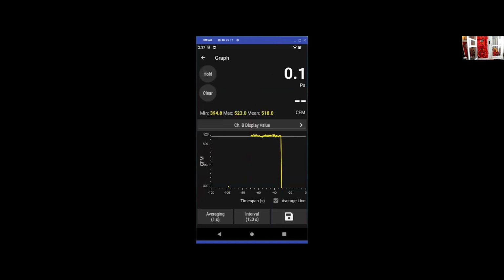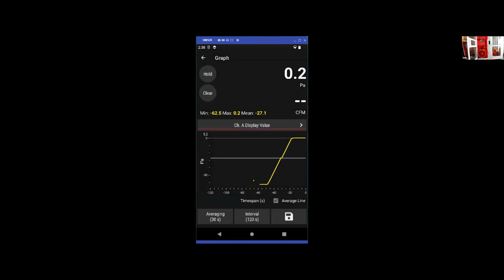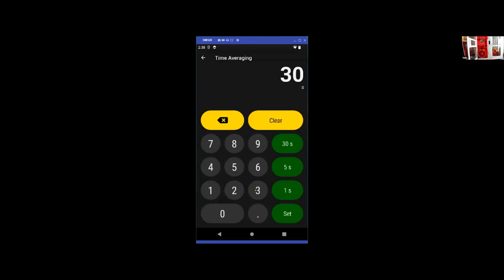One big change from the DM32 is if you change to 30-second averaging, you'd have to wait 30 seconds for those samples to collect. Whereas since we store historical data during runtime, if you change this averaging on the graph, it can help you dial in to find the proper averaging to account for any environmental effects like noise or other stuff you're finding within the building.